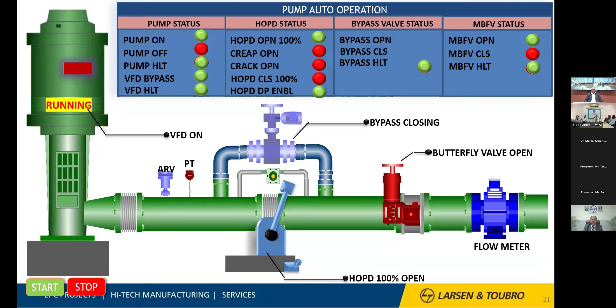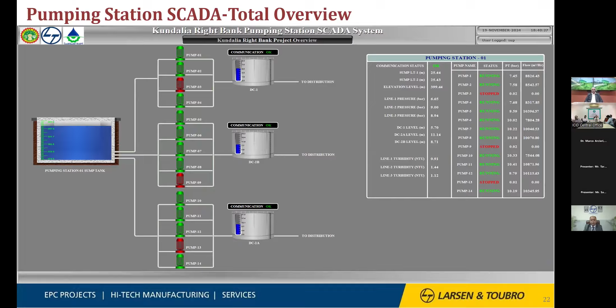Now, this is a live screenshot of our pumping system. All 14 pumps installed, 11 working, 3 standby. The 11 working pumps are denoted by the green color. Continuous monitoring of the inlet approach channel side water level is on the left side of these pumps, and on the right side we continuously get the water level of the DC, all the 3 DC. All the limits are set for what level an alarm will initiate through SCADA. If no action has been taken manually to control the supply, once it reaches the overflow level, the complete system will automatically stop through the PLC preset commands. No manual intervention is needed.